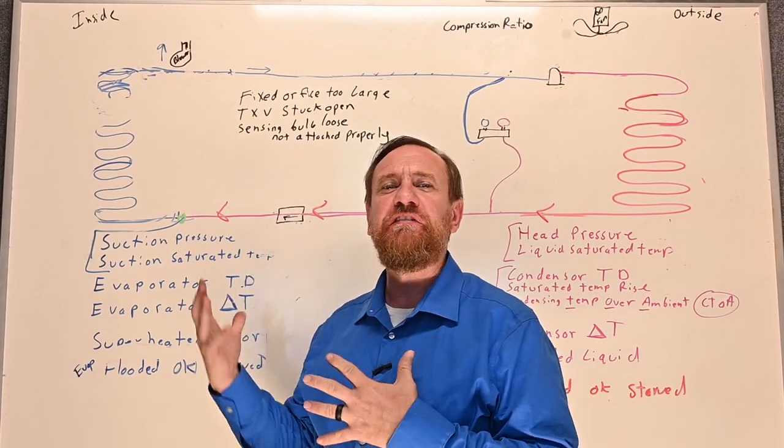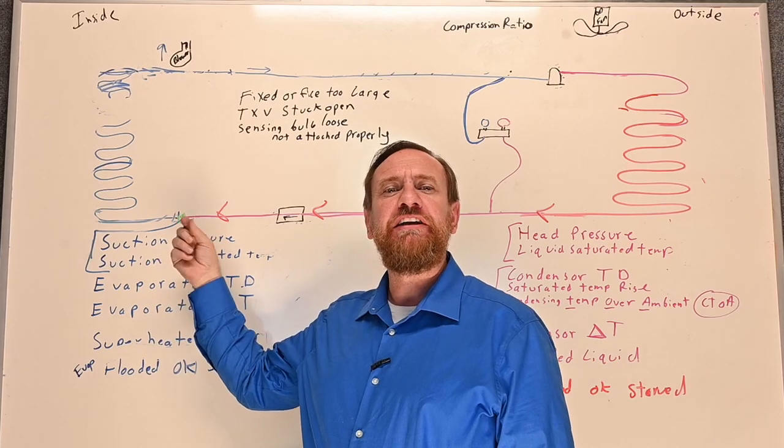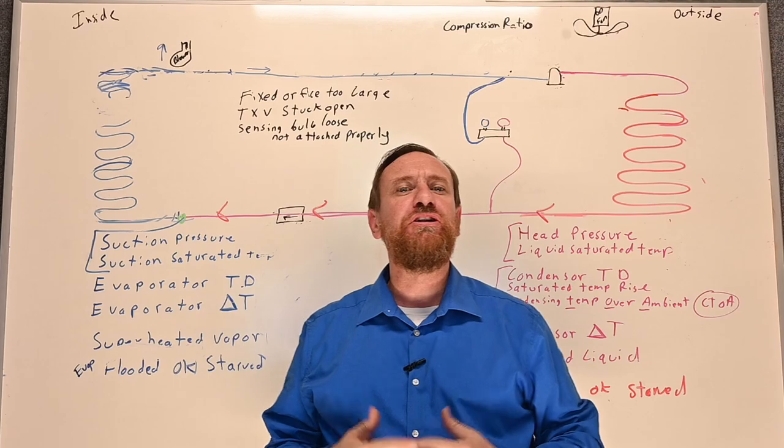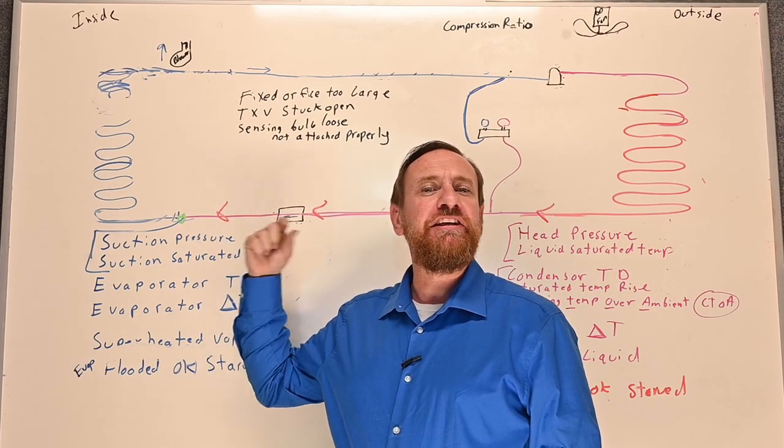Alright, for this one I'm going to categorize several of these together. Let's say that our metering device, our fixed orifice metering device, is too large. Remember, our metering device should match our compressor. A lot of times I'll see people leave the wrong metering device here, and that metering device is too large.